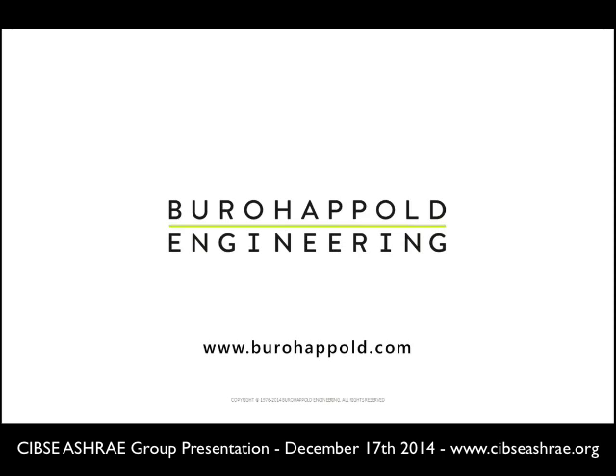There is, and it is. All of these technologies are widely looked into and studied, but the cost of energy in nearly all of the GCC countries is quite low. The solar energy payback is attractive, but it faces challenges of maintenance and, as I said earlier, the issue of baked sand on efficiencies. Solar energy with absorption chillers is very difficult to derive payback from, because absorption chillers are that much more expensive, adding to the overall cost of the sustainability energy solution. So in terms of capital cost and long-term payback, it's very rare - I have not seen an installation successfully put in unless it's a study.